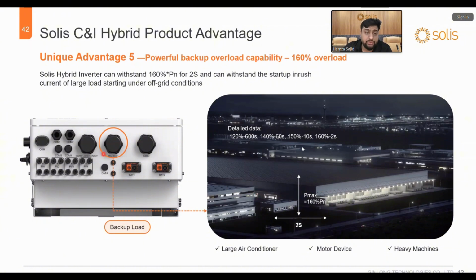So the backup load connected over here, if the load is 120%, it can last up to 600 seconds. If the load is 140%, it can last for 60 seconds. If the load is 150%, it can last for 10 seconds. And if the load is 160%, then it can last for 2 seconds. Actually, if you are targeting the C&I market, there will be a lot of loads that take inrush current or a lot of torque when they start. So the inverter can easily be utilized there to support the load.